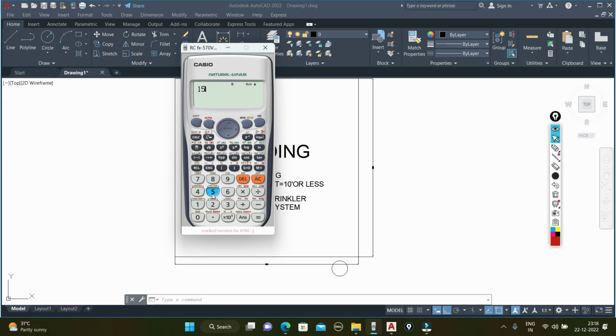It means 1500 minus 510. Our area of operation, or remote area, or design area will be 990 square feet. We will consider only this area to determine our firefighting system, or sizing the pipe or sprinkler, or whatever things we will see in an upcoming video.